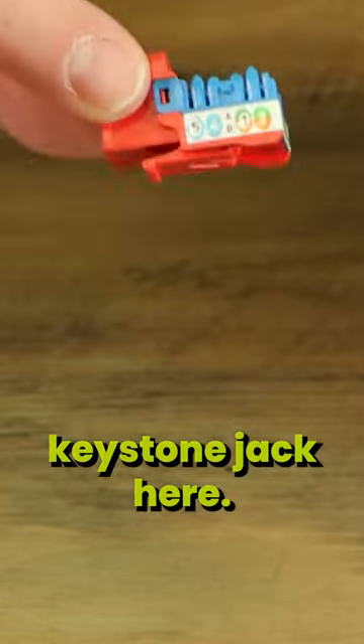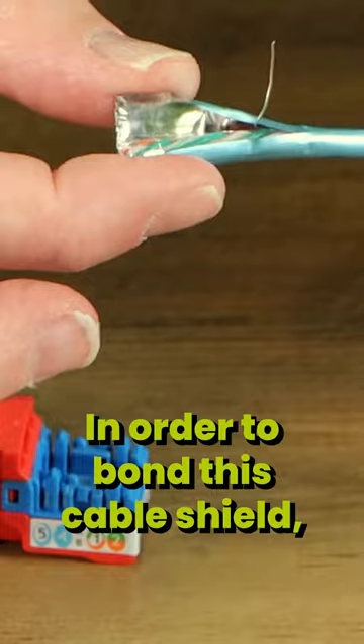In this case, we have an unshielded keystone jack here. There's no metal on this particular keystone jack on the outside in order to bond this cable shield.